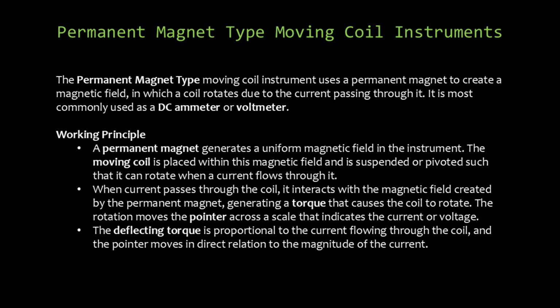Permanent magnet-type moving coil instruments are precision measurement devices that excel in direct current applications. A powerful permanent magnet generates a uniform magnetic field, within which a movable coil can rotate freely. When current passes through this coil, it interacts with the magnetic field, creating a torque that moves the pointer across a calibrated scale. The brilliance of this design lies in its linear relationship between current and pointer movement. Each increment of current produces a proportional deflection. This makes these instruments supremely accurate for DC measurements, serving as reliable sentinels in electrical systems.